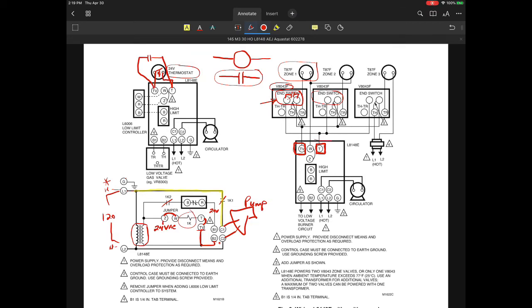And the way you'll notice this, they're also completely isolating. Every one of these zone valves has a separate set of contacts that are going to be in parallel, that are isolated, that will allow you to energize your T and TV to provide that path. Anything more than 2, you definitely have to put the Aquastat, the extra transformer, in here to power that system.